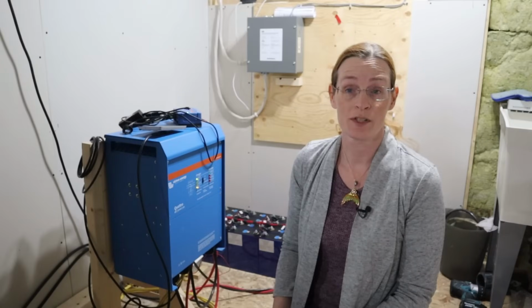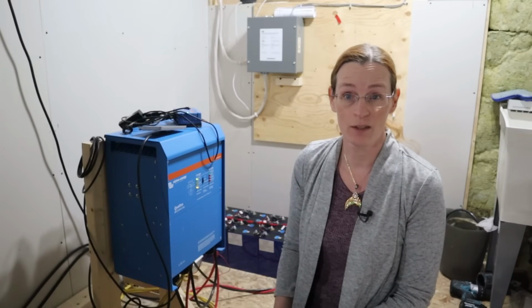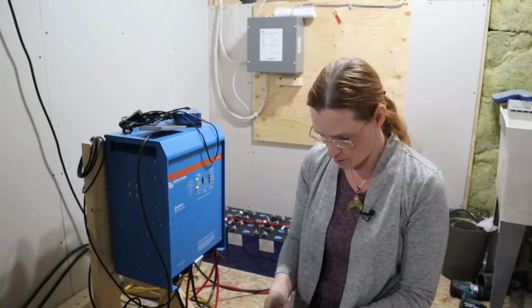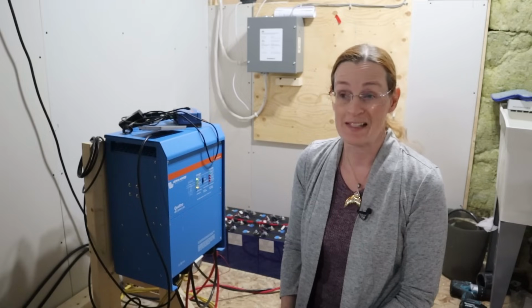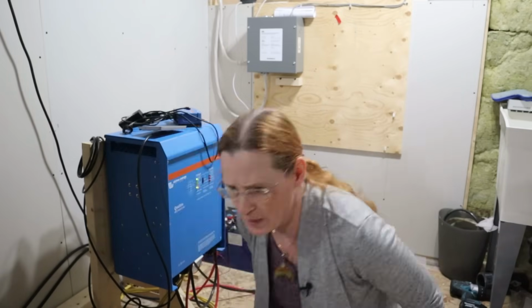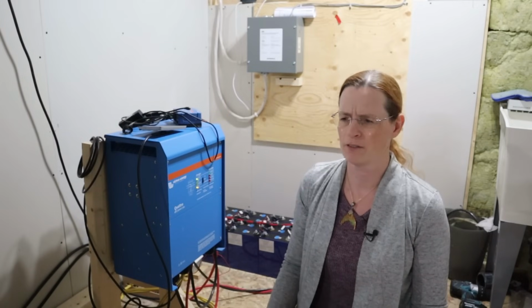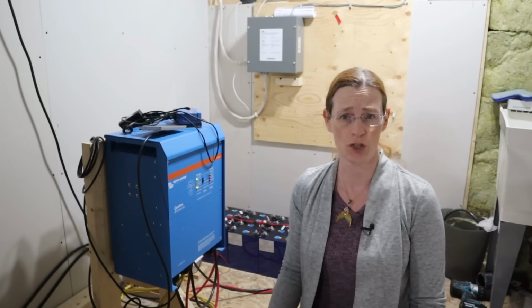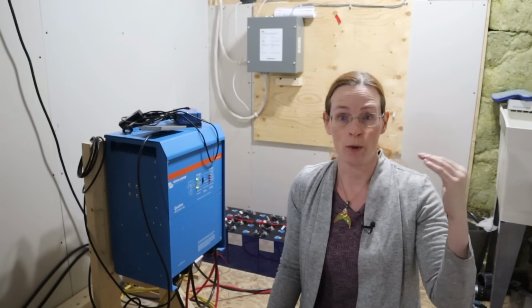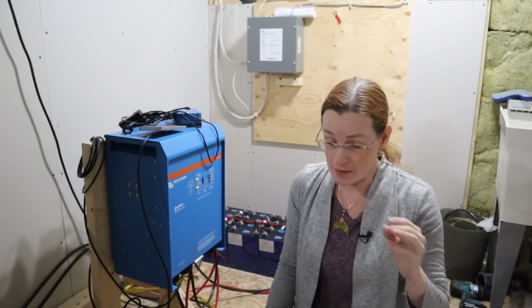Cell 12 was the lowest, as we saw, but it actually didn't take long to catch up with the rest. So I left it sitting for a while, and I noticed the charge current dropped off quite a bit. And I realized, wait a second, I set the float voltage too low. The absorption voltage is where... I'm going to try to explain this as best as I can.